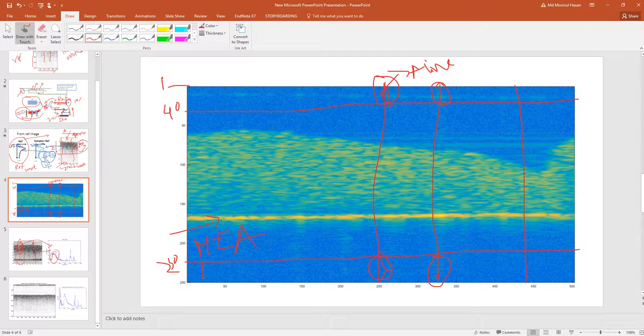Our goal is to make sure that when there is no tissue, there should not be any noise. Ideally, after subtraction of noise, the SNR of this part where there is no tissue should be 0, and when there is tissue, there should be a certain amount of SNR, whatever it is.